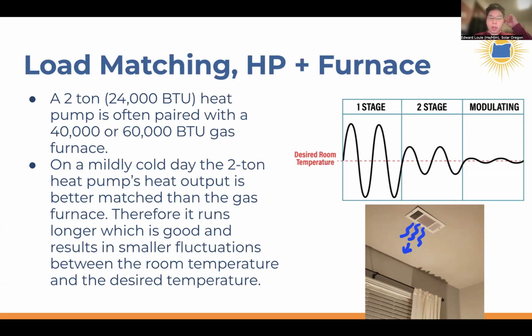And the reason why many gas furnaces are oversized is, well, one is tradition. The homes in the past used to be much leakier, much more poorly insulated than homes of today. And so gas furnaces back then were manufactured and sized for those very leaky homes. But the other thing is just the nature of burning a combustion fuel source. It's a higher energy density process. It generates a much higher temperature flame, a much higher temperature air, and so that's also one of the reasons why gas furnaces have higher outputs.